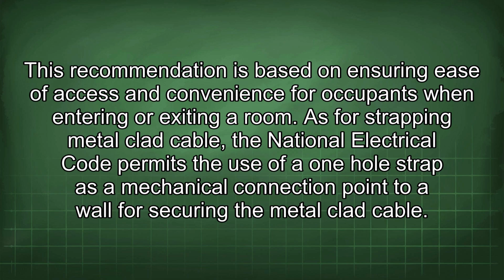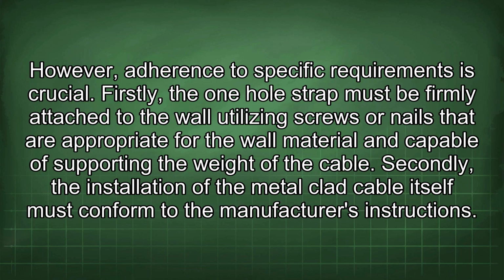As for strapping metal-clad cable, the National Electrical Code permits the use of a one-hole strap as a mechanical connection point to a wall for securing the metal-clad cable. However, adherence to specific requirements is crucial. Firstly, the one-hole strap must be firmly attached to the wall utilizing screws or nails that are appropriate for the wall material and capable of supporting the weight of the cable.